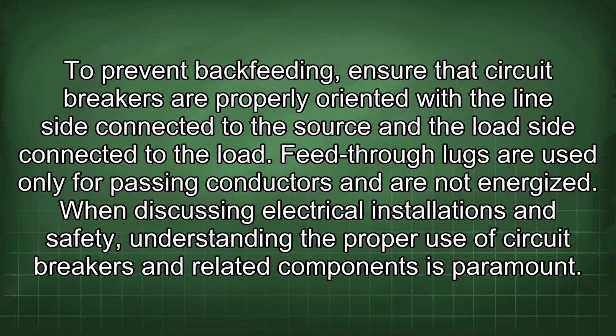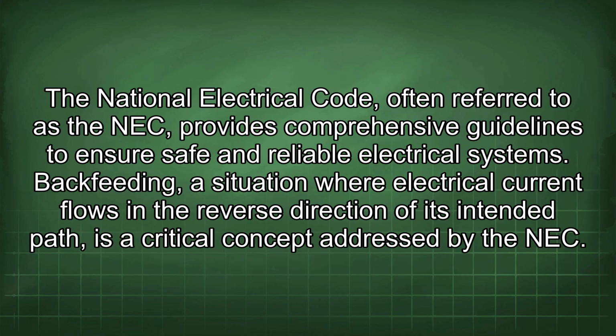To prevent backfeeding, ensure that circuit breakers are properly oriented with the line side connected to the source and the load side connected to the load. Feed-through lugs are used only for passing conductors and are not energized. When discussing electrical installations and safety, understanding the proper use of circuit breakers and related components is paramount. The National Electrical Code, often referred to as the NEC, provides comprehensive guidelines to ensure safe and reliable electrical systems.